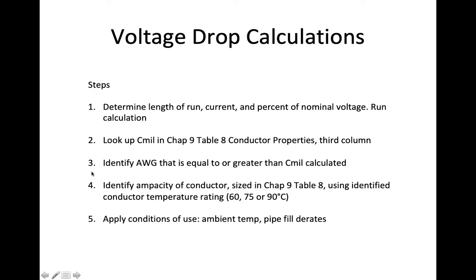Step 3. Identify the AWG, or the gauge size, that is equal to or greater than the Cmil calculated in my equation. Number 4. Step 4. Identify the ampacity of the conductor, sized in Chapter 9, Table 8, using identified conductor temperature ratings of 60, 75, or 90.